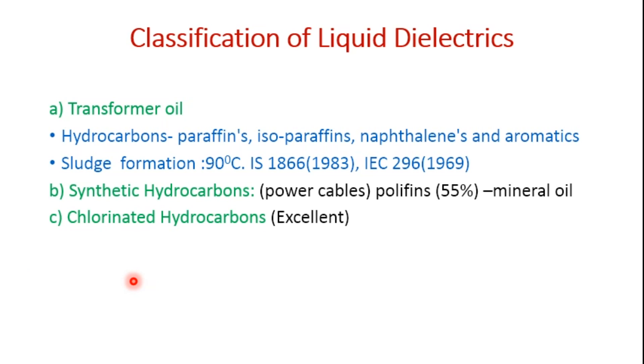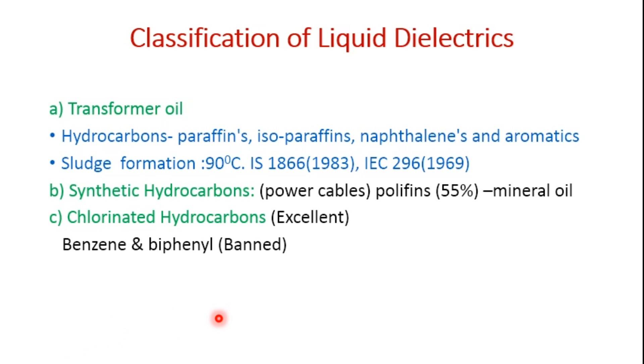Then we have chlorinated hydrocarbons. These are composed of benzene and diphenyl, which are chlorinated to produce a chlorinated aromatic compound called askarels, or simply PCBs. These have high fire point and excellent electrical properties, but they have been banned because of serious health hazards.